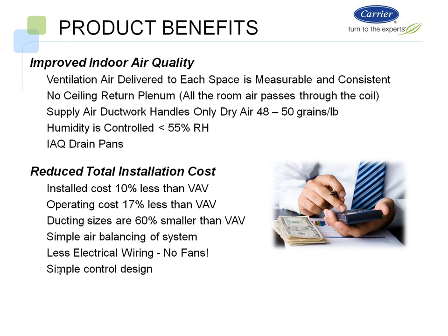And again, the controls get much simpler. If you're going to design a VAV system, you're typically going to have a DDC controller in each and every unit. With a chilled beam, you don't really need to do that. There's a space sensor there in the wall. You have a set point. It can either be a thermostat or it could be a DDC system with a sensor. And then you open a two-position valve, and the water will flow through that unit and maintain that space condition. So very simple control.